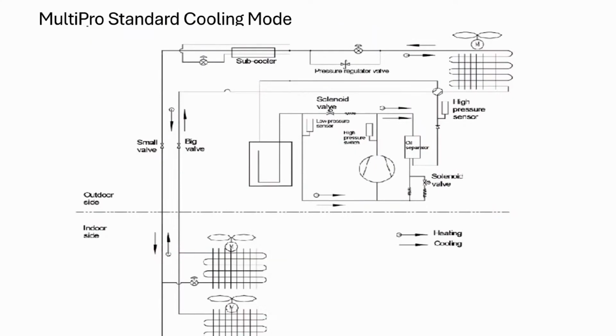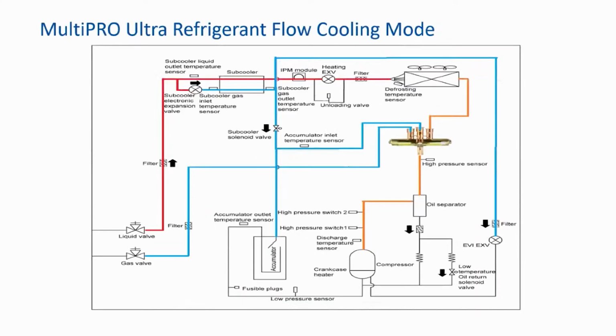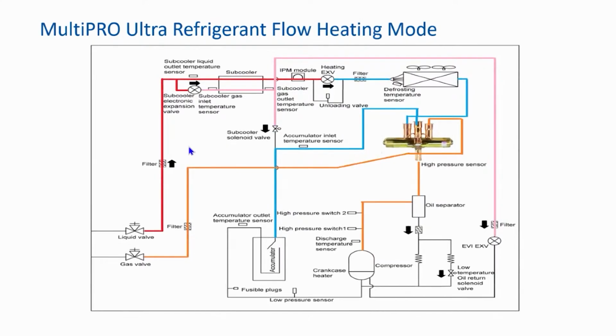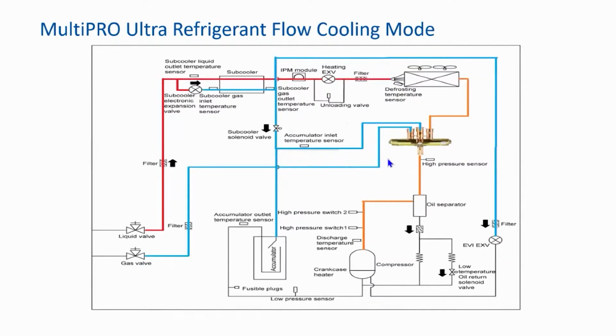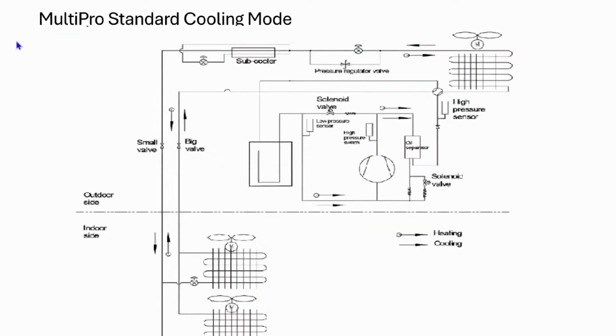And if I go back to my piping diagram, this is the way GREE does them. They just have this little circle up here, which to me is a little more confusing than when I actually change up the diagram. So this is their diagram. All I did, and had put in the service manual, was take out their little circle and make an actual reversing valve. We didn't change the piping at all. And the same with heating mode, just showing your whole flow through and highlighting it, making it a little easier to read. When time allows, hopefully we can highlight this diagram a little bit better and actually do a reversing valve picture in there.